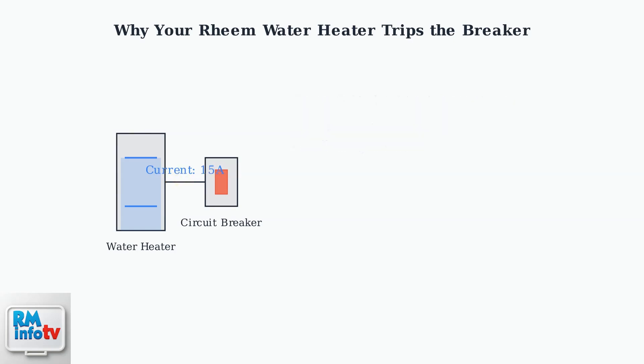Damaged wiring, loose connections, or pest damage can create electrical faults. These issues cause irregular current flow and can make the breaker trip unexpectedly.